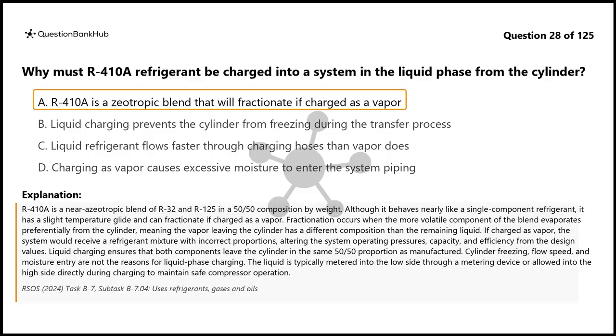If charged as vapor, the system would receive a refrigerant mixture with incorrect proportions, altering the system operating pressures, capacity, and efficiency from the design values. Liquid charging ensures that both components leave the cylinder in the same 50/50 proportion as manufactured. Cylinder freezing, flow speed, and moisture entry are not the reasons for liquid phase charging. The liquid is typically metered into the low side through a metering device or allowed into the high side directly during charging to maintain safe compressor operation.